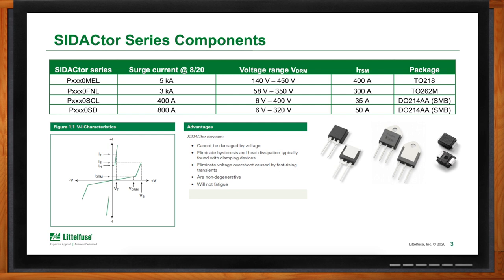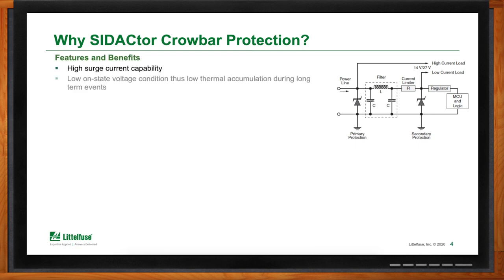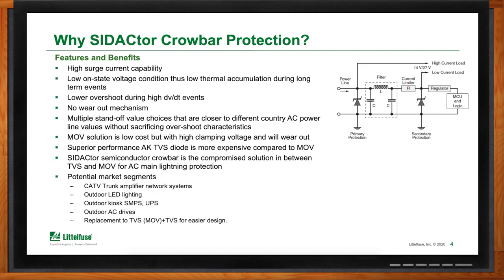Some of the features and benefits of the SIDACtor are its high surge capability and its low on-state voltage. Also, low overshoot during high dV/dt events — this is the rise time of a surge. Because this is a solid-state silicon component, there are no wearout mechanisms. As long as the device is operated within its datasheet specs, there is unlimited capability. We also have multiple standoff values and different voltages. It can be used in cable TV trunk amplifier network systems, outdoor LED lighting, switch mode power supplies, AC drives, and as a replacement for MOV-TVS or inductor-TVS combinations.